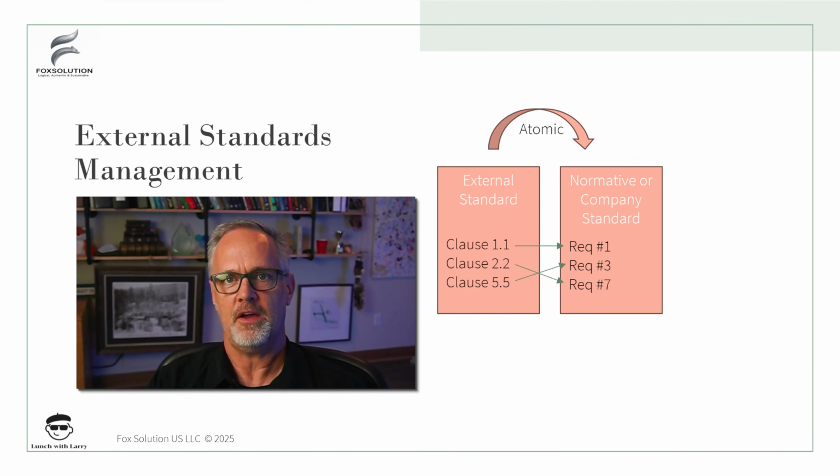For example, if you have a sterilization document and the product line is syringes versus maybe pacemakers, you're going to deploy ethylene oxide sterilization differently for those. In some ways, it's the same. The external standard is going to give you that generic view. But how you're going to deploy it for this device type is likely to be different inside your company. And it's also intellectual property as to how it is that you're going to do that.